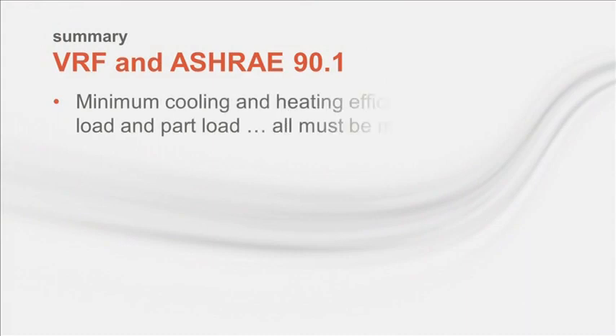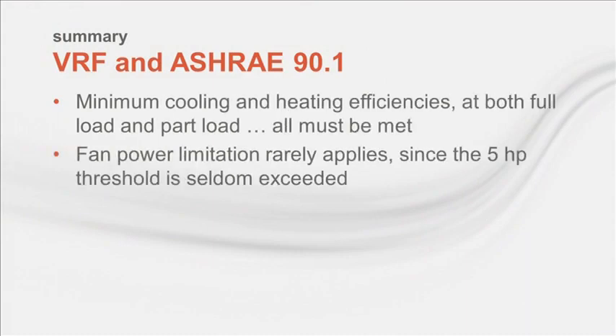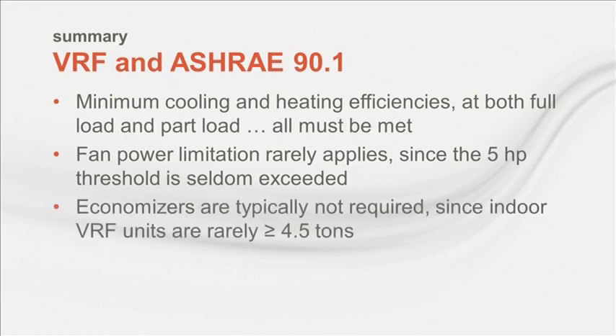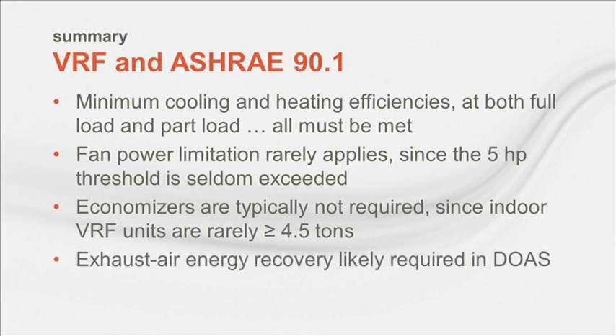So to summarize what I heard, 90.1 includes minimum efficiencies for VRF equipment, but it's unlikely that the indoor unit fan will exceed the 5 horsepower threshold, so the fan power limitation likely does not apply. For the same reason, economizers are probably not required due to the small size of the VRF terminals, but exhaust air energy recovery is probably going to be required in the dedicated outdoor air unit.